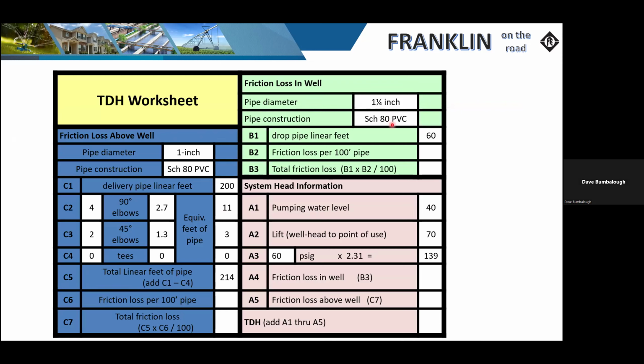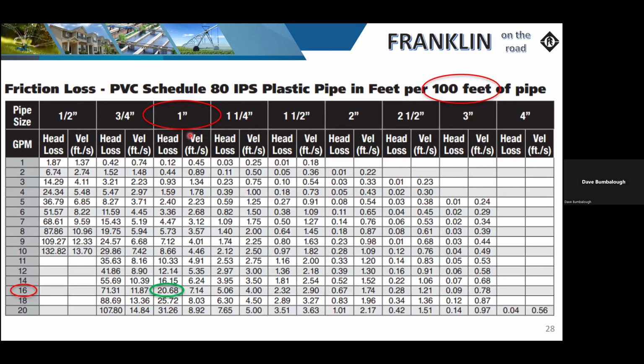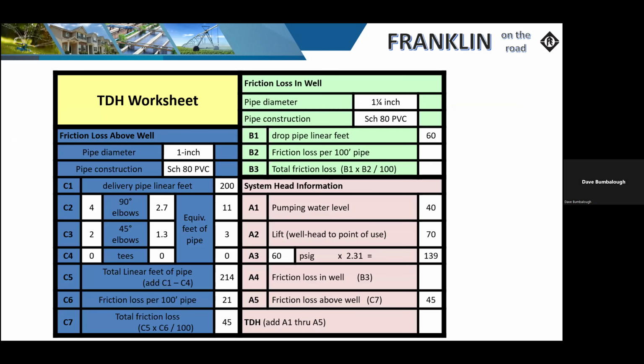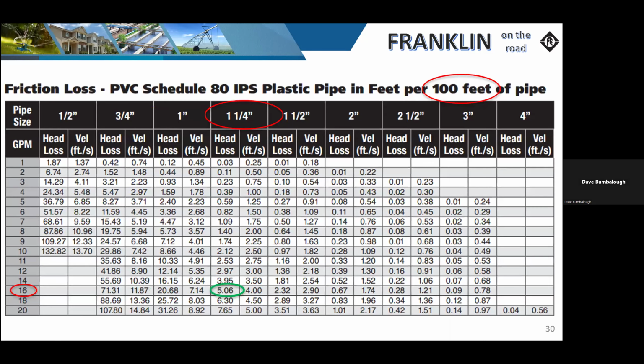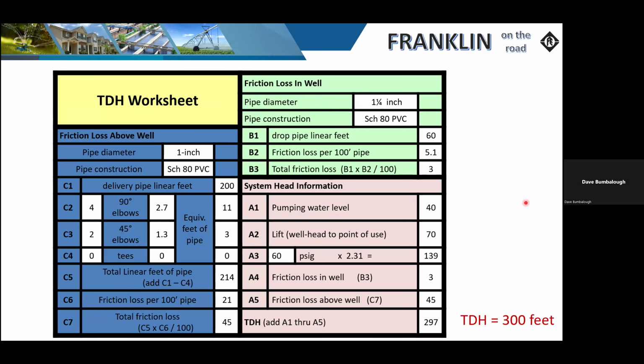Friction in the well, we're going to take a look at that as well. On this next one, we look at the chart and say, okay, we're 1-inch pipe. We're at roughly almost 21 foot of head loss per 100 foot. Now, granted, I just rounded it up. We're looking at 15 gallons per minute, but in this case, we're just going to use 20 as our number. So going forward, we plug those in and see that in this case, 1.25 inches is going to be a friction loss of about 5.1.